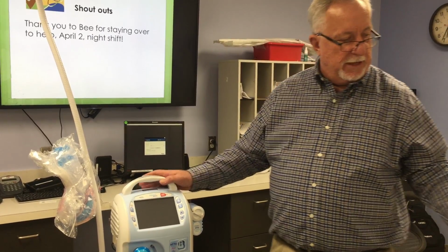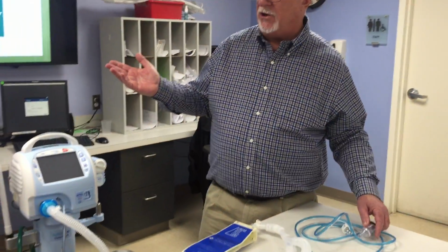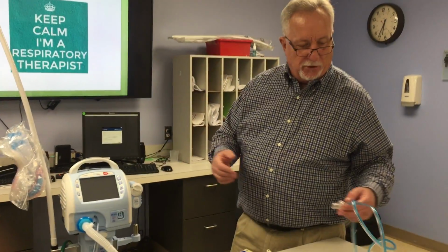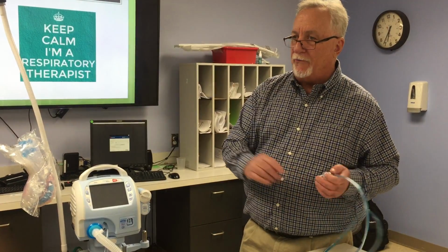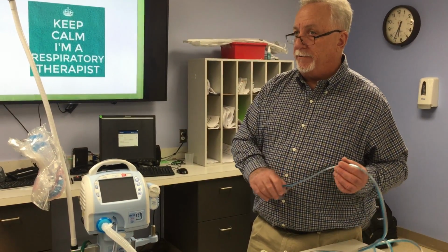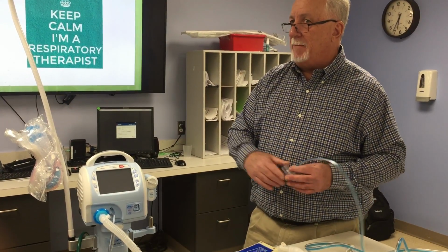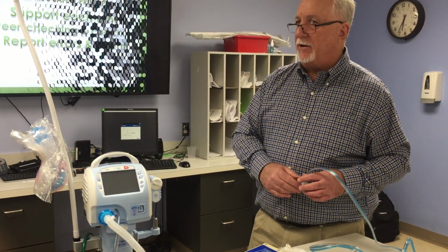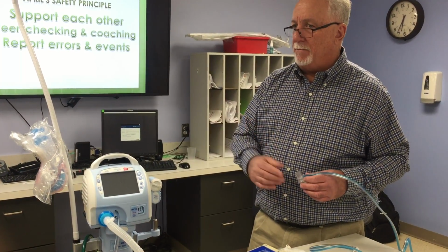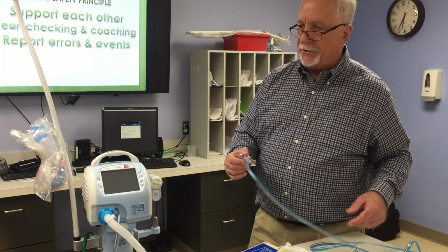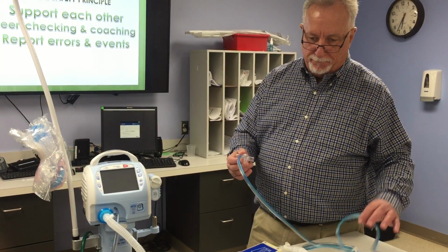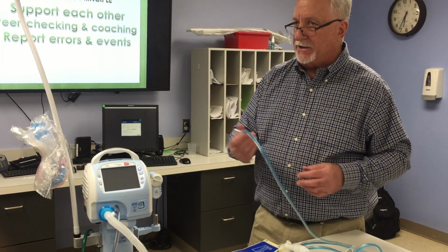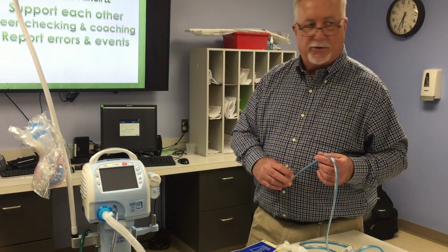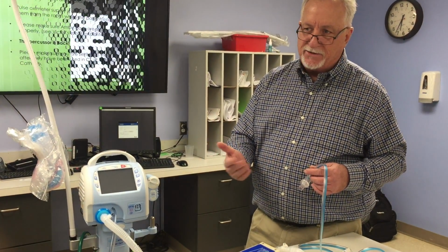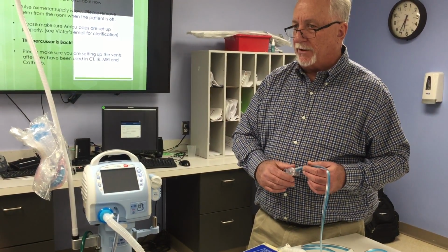And the other thing, you know, and again, maybe if it's a sicker patient you're going to transport, the flow sensor will allow you to go from pressure triggering to flow triggering. So, and that might be more of a pediatric or kids thing, where you maybe want a flow trigger instead of a pressure trigger. But that's one of the advantages too with using the flow sensor as well. You'll get your exhale volumes, and then you get flow triggering as well.